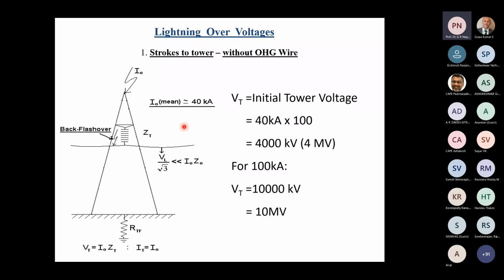A strike occurring from a normally grounded object, the tower, to the phase conductor. It's just the opposite of what we normally see: flashover from the high voltage object to the grounded object. But here it is the normally grounded object which attains a high potential and causes a flashover. So now you will see that 4 megavolts can cause a flashover here. So now for 100 kA, which is not very rare, the potential can be 10 megavolts. Remember, in the beginning I mentioned it can be hundreds of kilovolts to tens of megavolts. You see here, if it's 200 kA, it becomes 20 megavolts. That's all. It's not 20 billion volts.